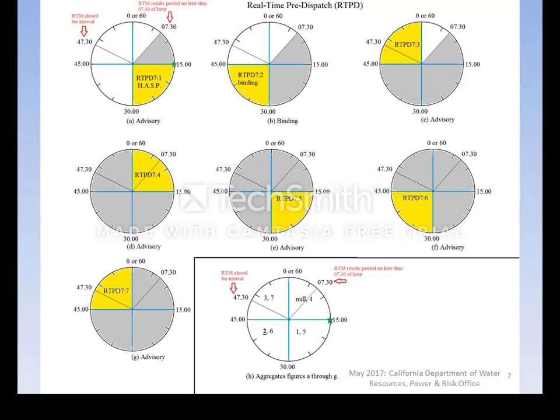Analyzing the figures on this slide: Figure A shows the 47-minute-30-second mark of the hour where HASP (PD7) samples the inputs, with computation completed by the 7-minute-30-second mark of the next hour. PD7 transmits unique instructions for a total of 7 fifteen-minute intervals — totaling 105 minutes — through ADS to all committed units. The instructions contain startups, shutdowns, and transitions between multiple generation levels. Intervals 1, 3, 4, 5, 6, and 7 are advisory, while interval 2 is binding. The PD7 instructions commence at the 15-minute mark of the hour.